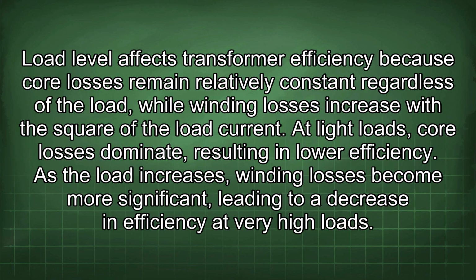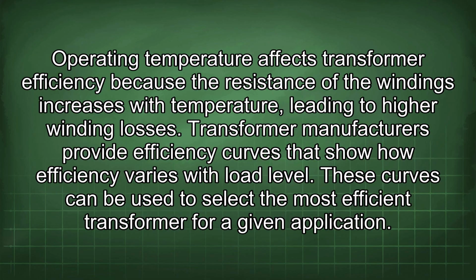Load level affects transformer efficiency because core losses remain relatively constant regardless of the load, while winding losses increase with the square of the load current. At light loads, core losses dominate, resulting in lower efficiency. As the load increases, winding losses become more significant, leading to a decrease in efficiency at very high loads. Operating temperature affects transformer efficiency because the resistance of the windings increases with temperature, leading to higher winding losses.